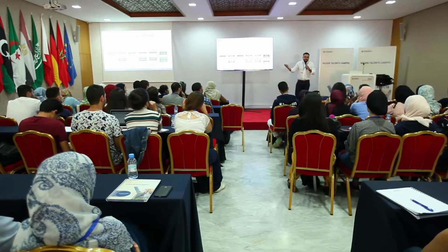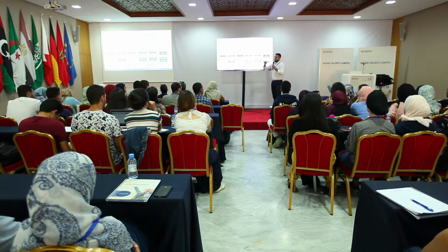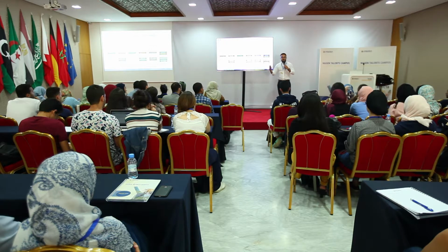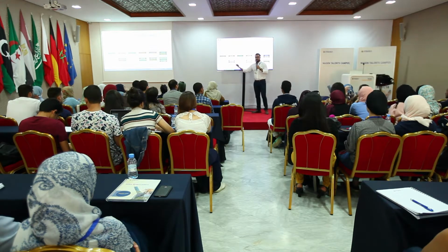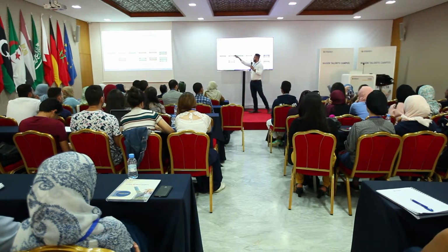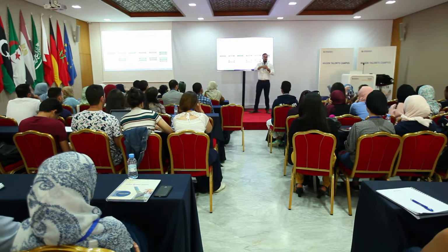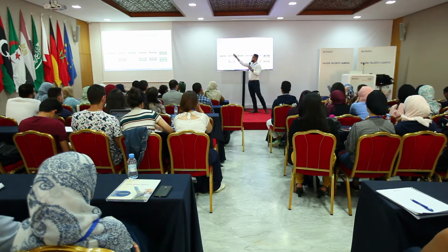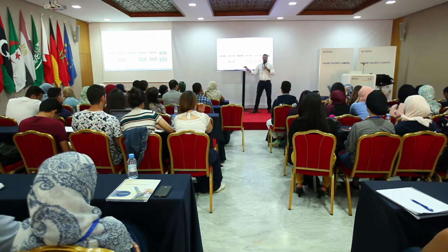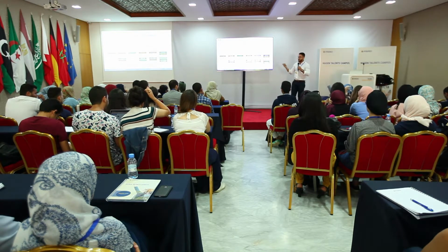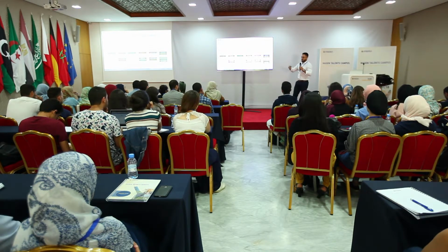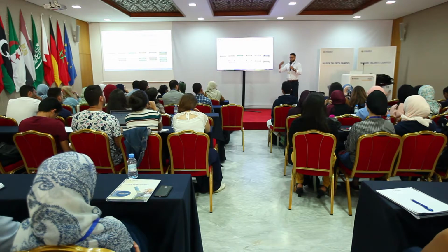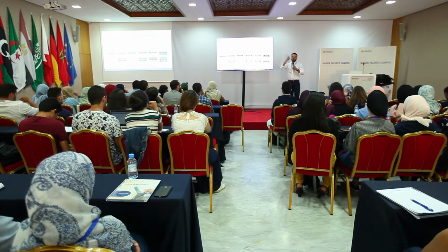So let's say this is a tower plant. In a tower plant, you have different blocks that you can distinguish. One block is the collector part, the solar part, so how I collect energy from the sun. One block is the storage and heat transfer fluid part, which is how the fluid gets hot, what do I do with it, how do I design that? And the other block converts the heat from this fluid into electricity, which is the power block cycle. All of them can be designed specifically. All of them have sizing design questions independently, both at subsystem level and at component level.